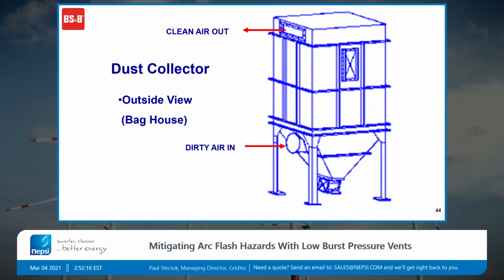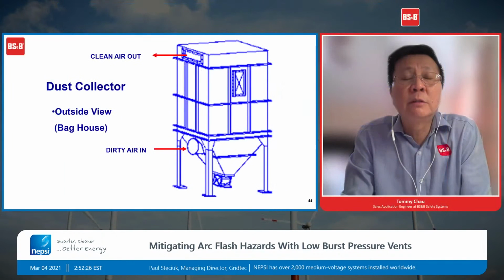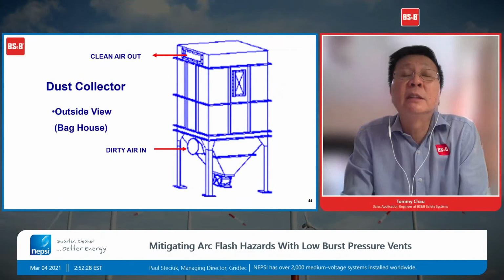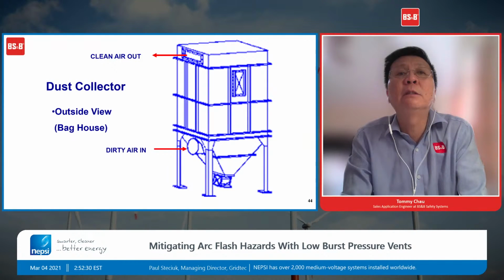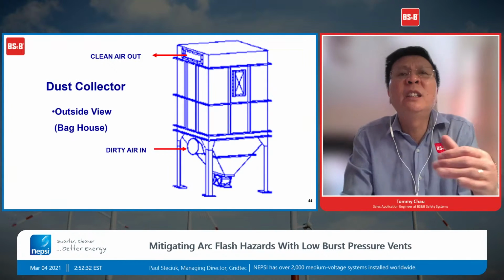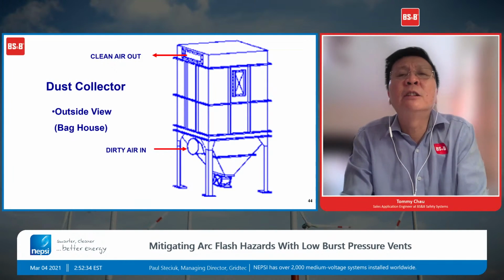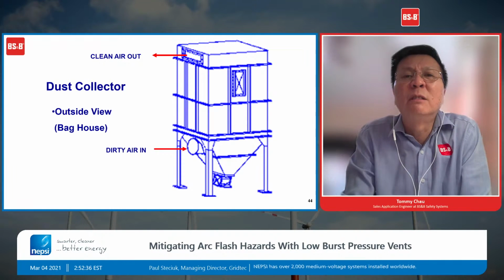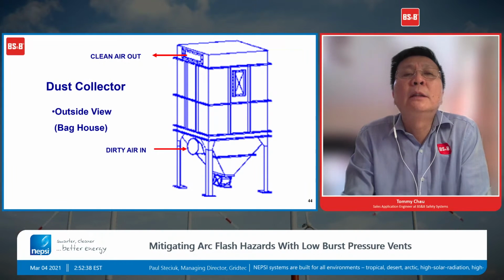This is just a cross-section view of the dust collector, and as you can see, you have the explosion vent toward the top there. Typically you want to put the explosion vent where your highest risk is going to be, which is where the dirty air is. The clean air typically doesn't carry a lot of higher risk. So this is just a view to show where you will typically mount the explosion vent on the dust collector.